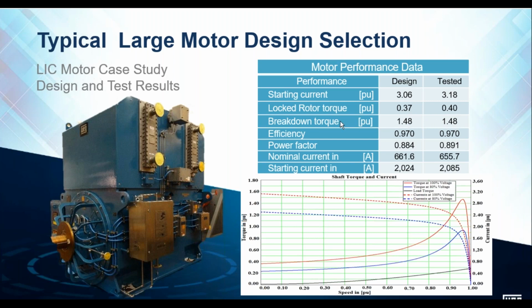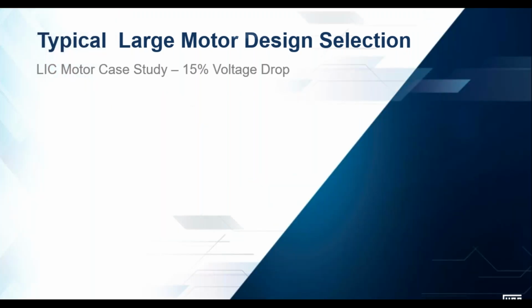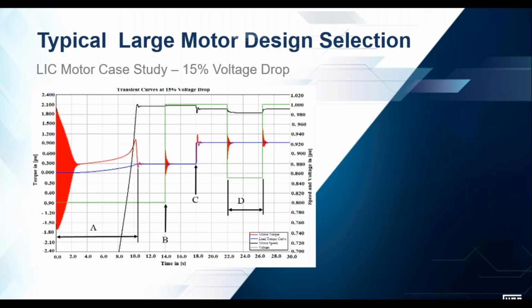So really, this motor was literally on its limit in terms of how low we could get the current on a standard design squirrel cage machine. Then before it left the factory, we wanted to test that the machine can operate within the parameters that were prescribed.